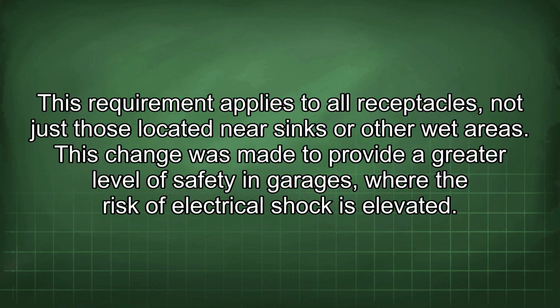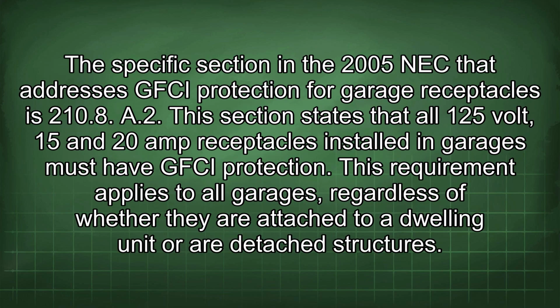This requirement applies to all receptacles, not just those located near sinks or other wet areas. This change was made to provide a greater level of safety in garages where the risk of electrical shock is elevated. The specific section in the 2005 NEC that addresses GFCI protection for garage receptacles is 210.8(A)(2). This section states that all 125-volt, 15 and 20 amp receptacles installed in garages must have GFCI protection. This requirement applies to all garages, regardless of whether they are attached to a dwelling unit or are detached structures.